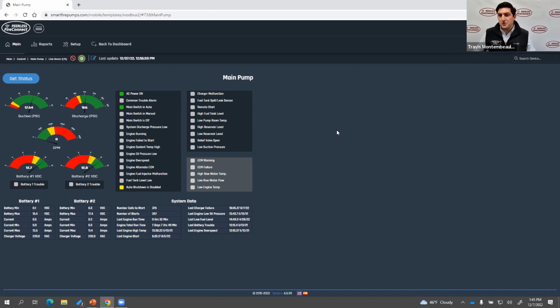For example, being able to look physically for any leaks. If you could do something like heat mapping, for example, and look at bearing temps. That's stuff that we want to take even further, to really allow somebody to maybe turn that pump on and go do something else, because everybody's really busy, right? So walk down the rest of the facility while the pump's running its weekly test. And then if a condition pops up, they get a text message and they go running back to the facility. And logging all that data effectively.